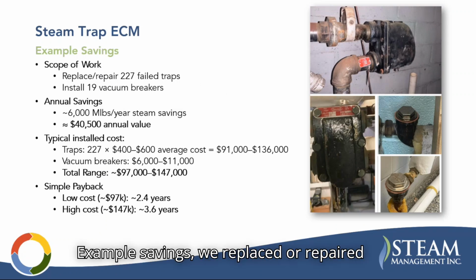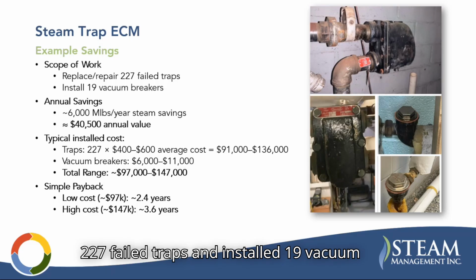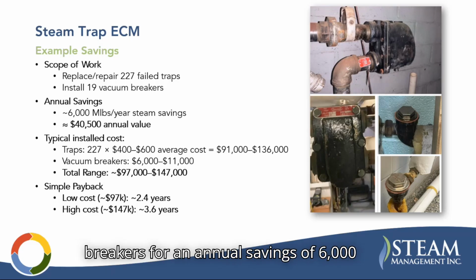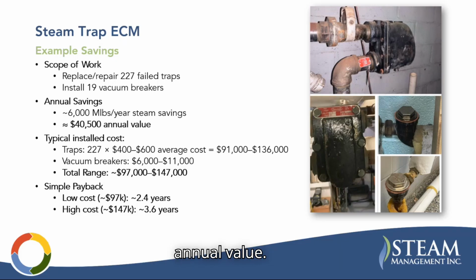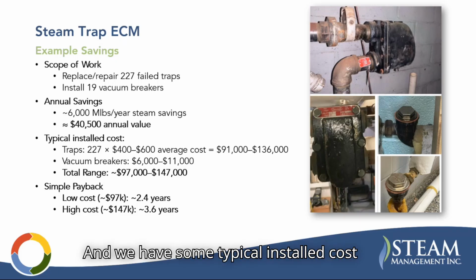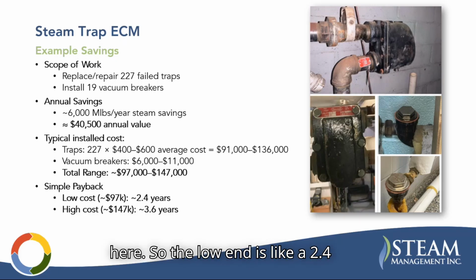Example savings: we replaced or repaired 227 failed traps and installed 19 vacuum breakers for an annual savings of 6,000 M-pounds per year, which is a $40,500 annual value. And we have some typical installed cost here. So the low end is like a 2.4 year payback or 3.6 year payback, from our cost. So that's a pretty good scope.